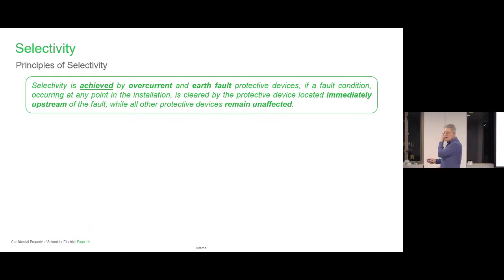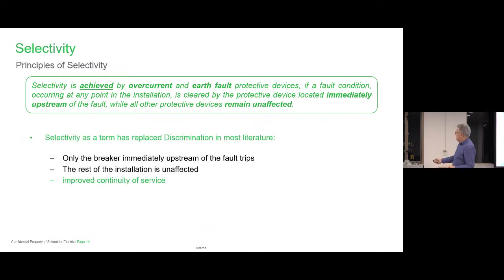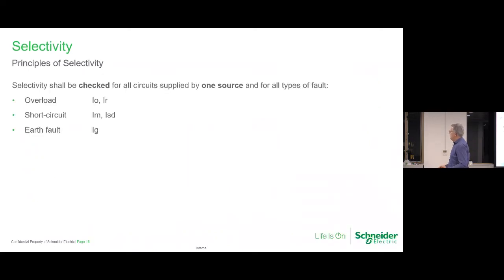We don't always achieve this, and we don't always necessarily have to, but it is something we want to aim for. This is where we can guide you through making subtle changes within the protection device selection, of not just the breaker, but also the trips and the way you set them. That's how you achieve selectivity. Sometimes even then you will fail because it's just not possible, but sometimes it's not necessary either. I can give you some examples of when it's not necessary. What we're after is improved continuity.